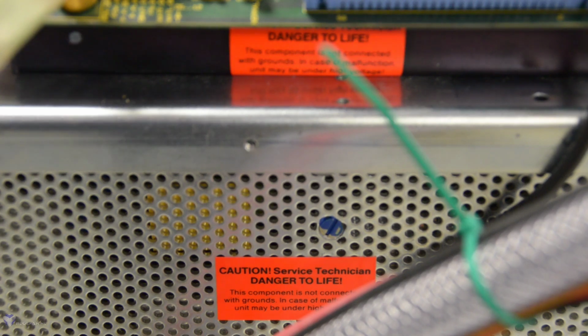Now this warning is actually quite relevant because the arc lamp is water cooled, and water and high voltage typically don't mix. Of course demineralized water is used, and usually the high voltage and water are not in contact with each other, but if the arc lamp fails, and that can happen due to old age, it can break and water can enter into the arc lamp and come in contact with the high voltage terminals. So then you rely on the water insulation to actually keep the high voltage out. So it's good to realize that when you mess around with these lasers, you know what you're doing, because there is high voltage in there, besides of course the high output power optically.